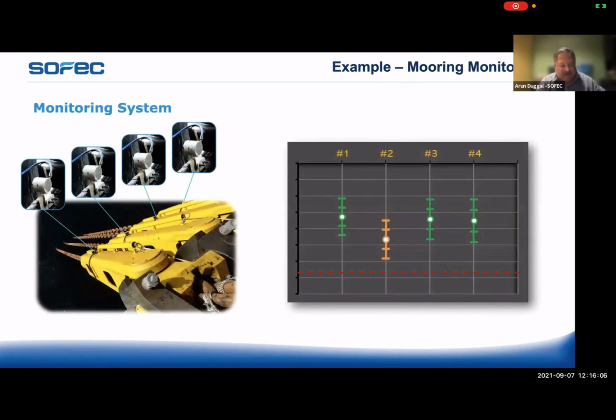What we have now in most of our anchor leg monitoring systems is a way in which we take some more data from the vessel, and we process the data on board the turret. We send the data to the vessel control room. And at that point, we can give some indications where we're tracking the data, and we're providing a kind of graphical look at, say, line tensions in a group of 4 legs at one corner of the turret, or one of the chain tables. And that allows us to detect, and you can see here also with the color scheme, whether it's tracking within the expected range or whether it's falling out of it. The red dotted line is sort of the alarm limit. So this is what we've been doing now for the last 5 to 10 years.